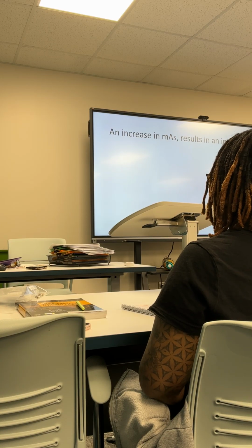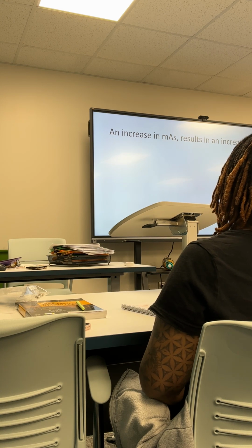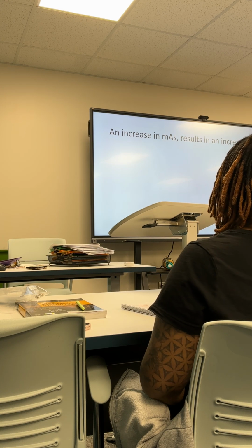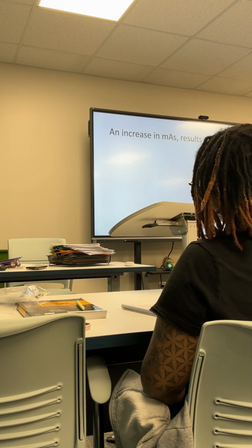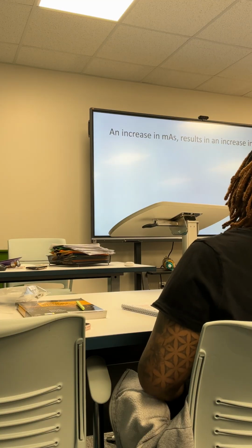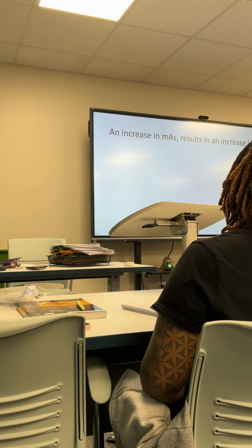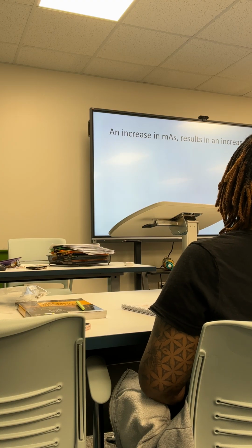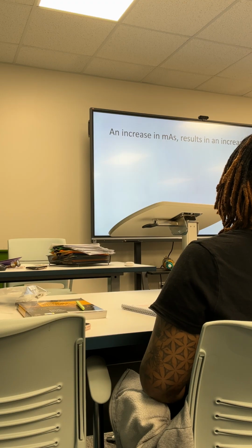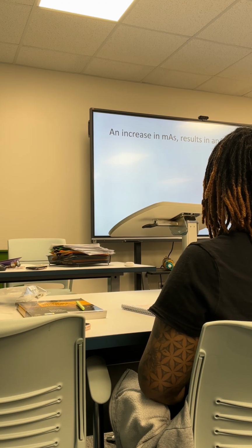So number one controlling factor of intensity was first mAs, then kVp. I just wanted to show you that, but we'll talk more about it. So just put them all out. They're directly related, but at a different rate because of the square for kVp. Okay? We'll talk more about it. I was thinking, you want less, so mAs is easier to get less, but kVp is harder to get less.